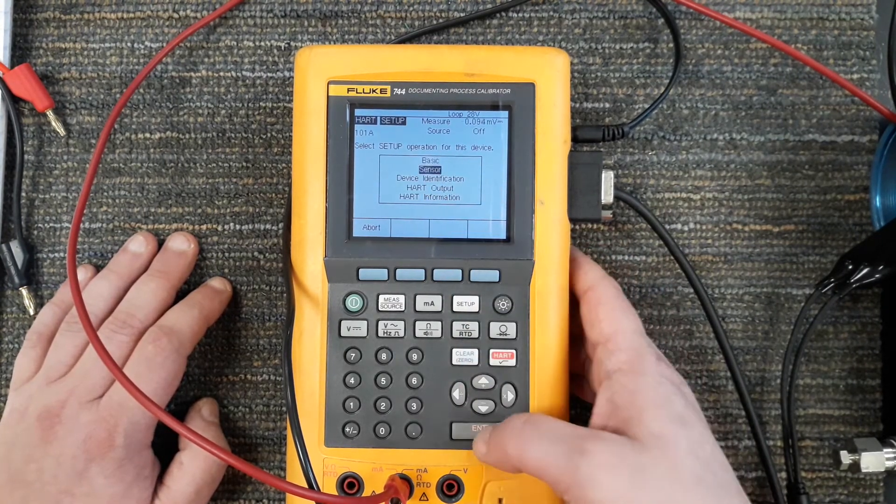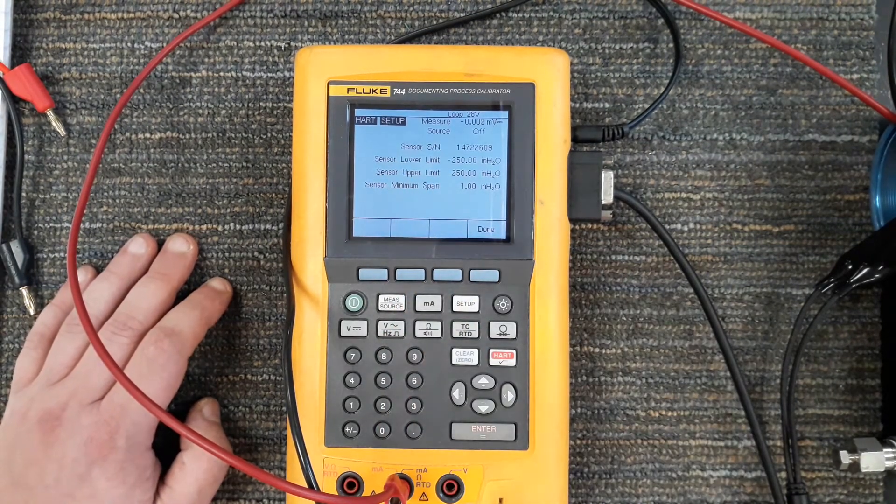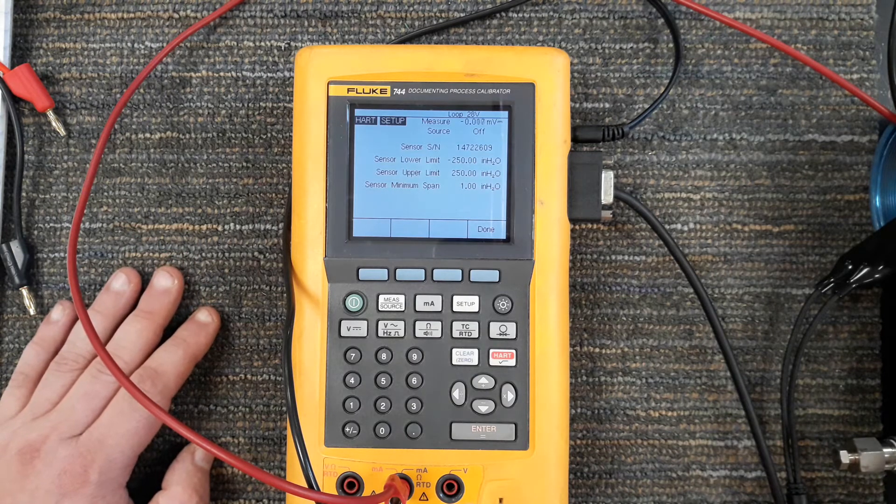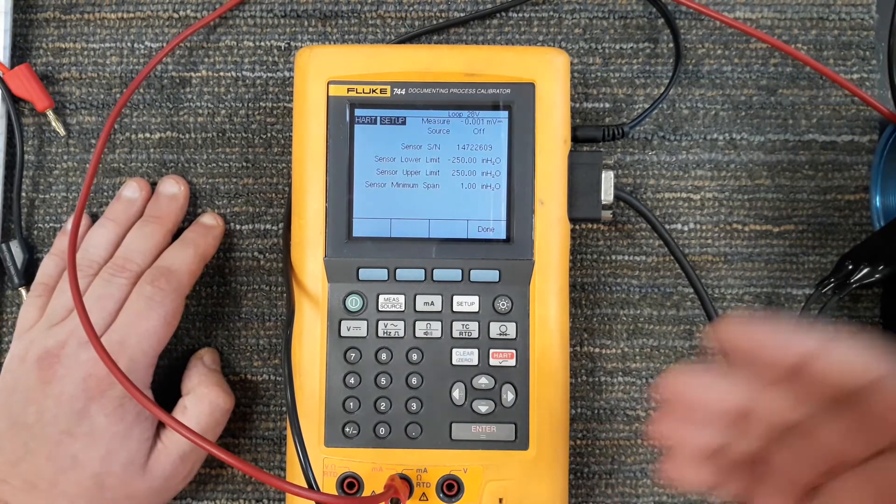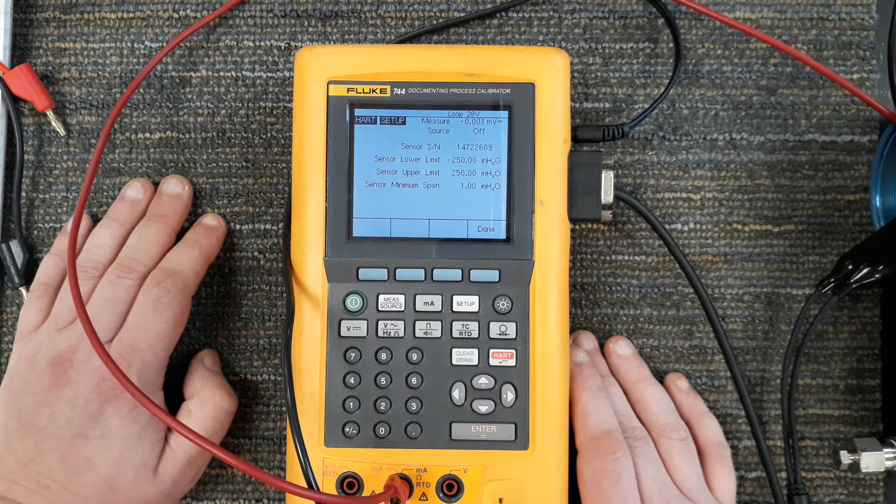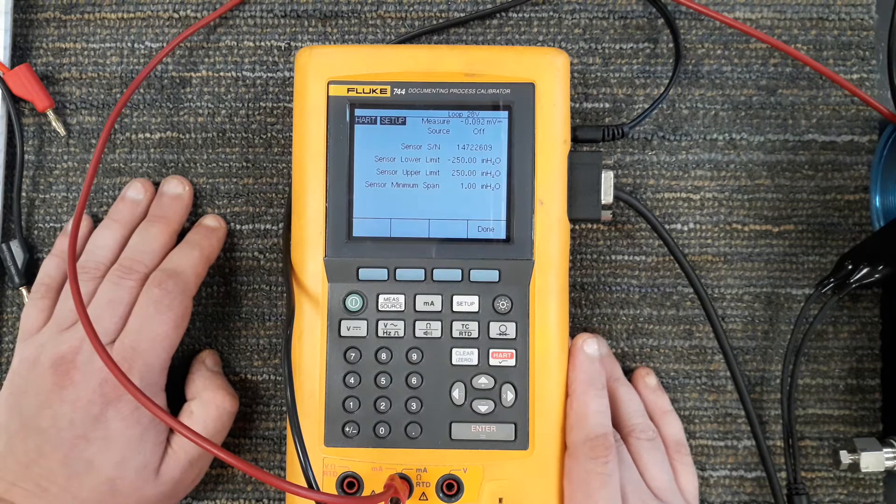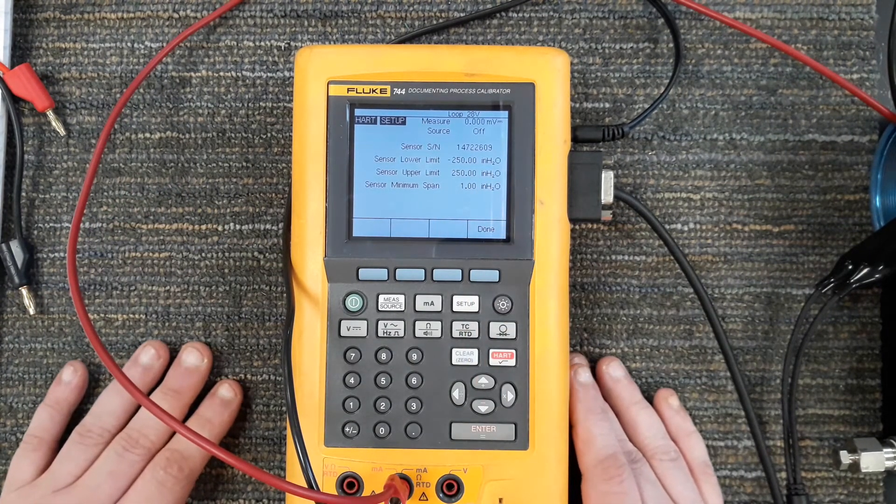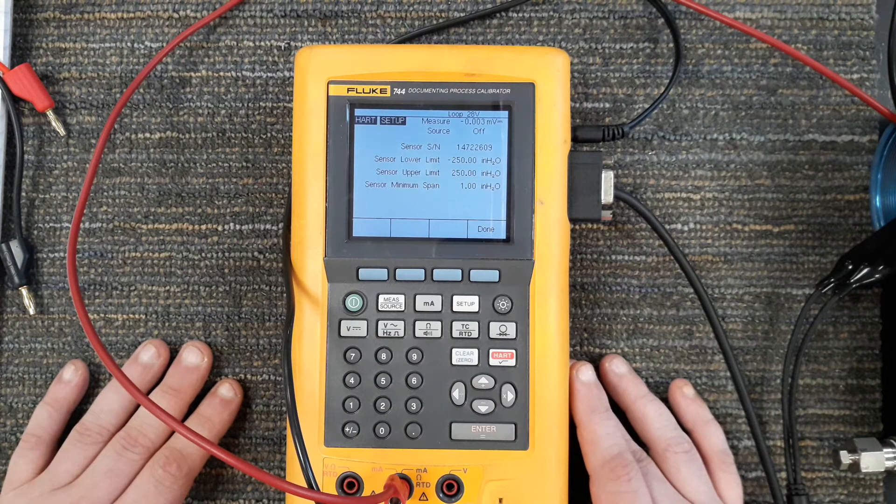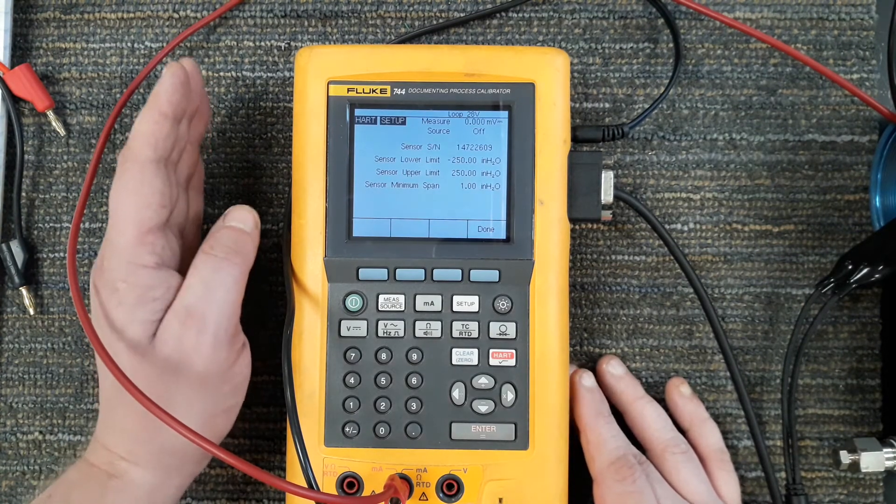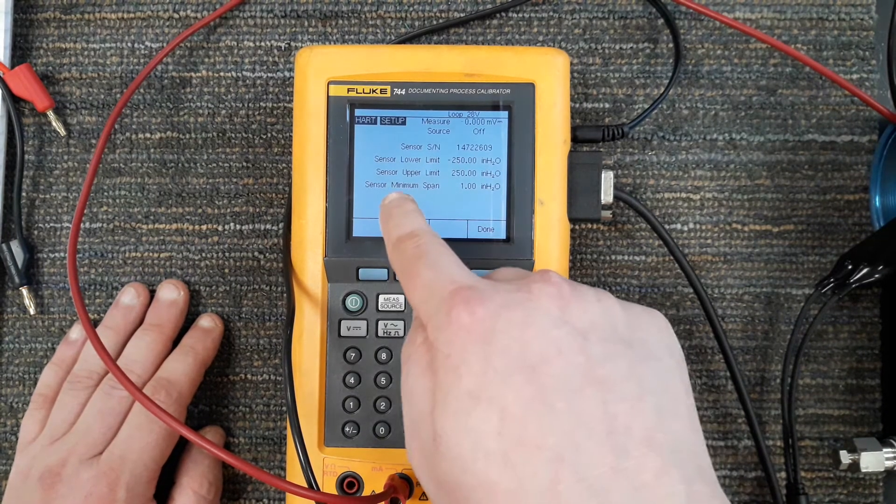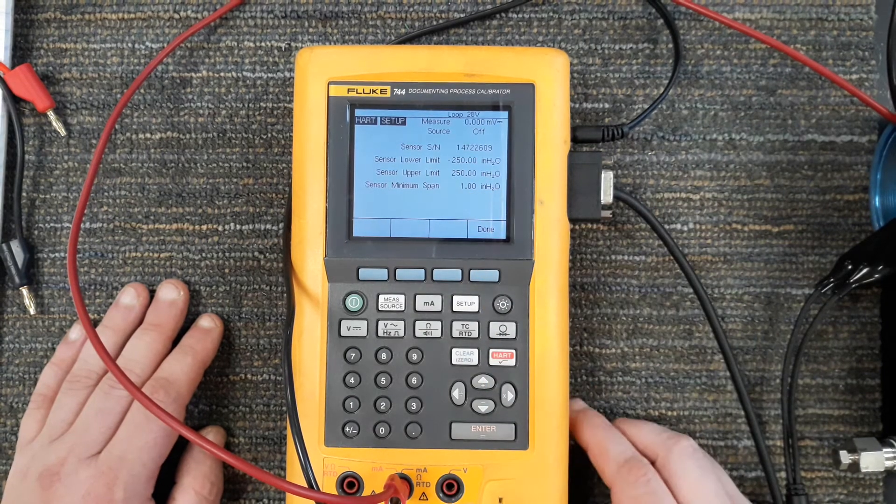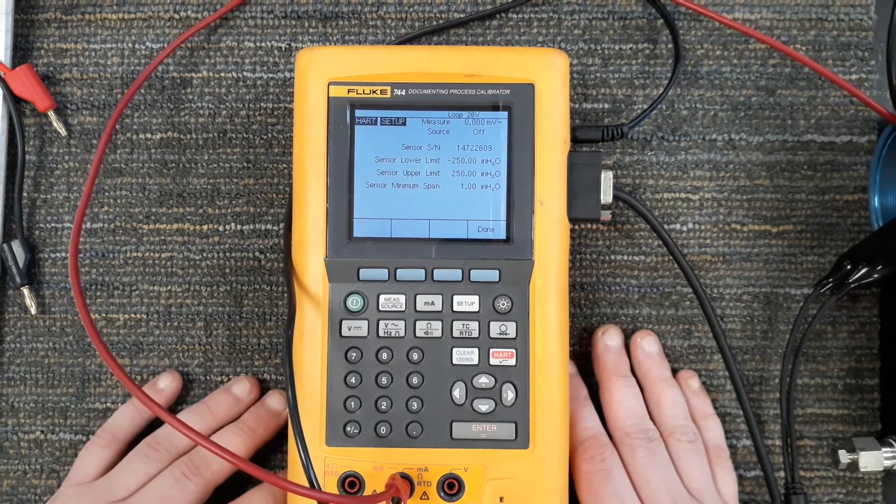I can go into sensor setup and it's telling me what the sensor limits are. This transmitter's limitations on its diaphragm sensing elements is negative 250 inches water column up to 250 positive, so a span of 500, but the minimum span is one. What that's telling me is I can set a URV and an LRV, they have to be at least one inch of water column apart. I can't say I want my LRV to be zero and my URV to be 0.5. Minimum sensor span is directly tied to its accuracy. If you're trying to have a span less than one, chances are you're not going to get the accuracy of a number you want. You'd go with a different model.